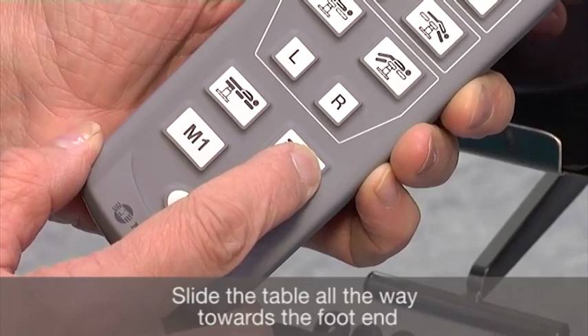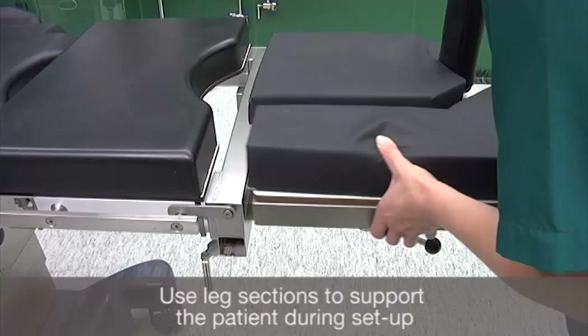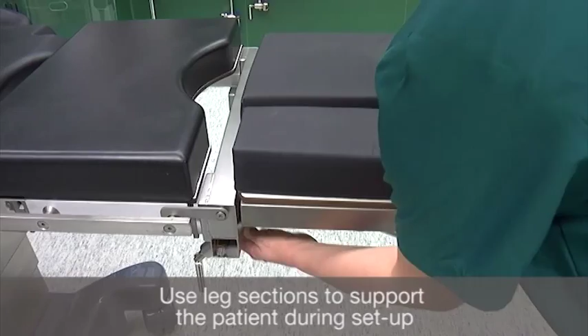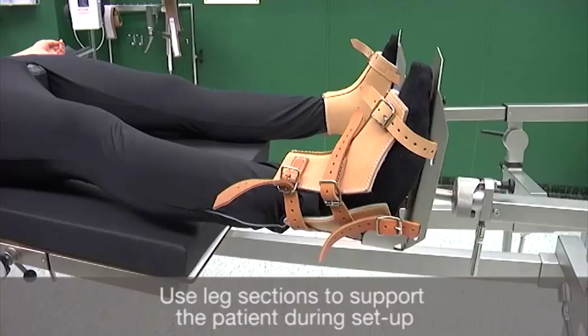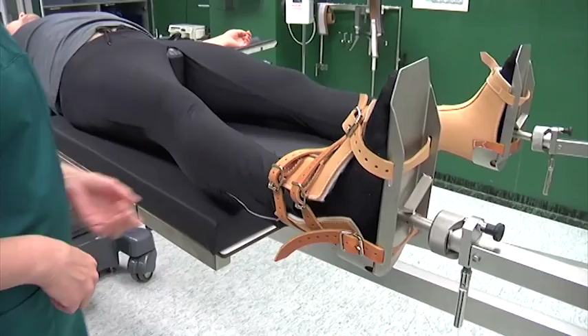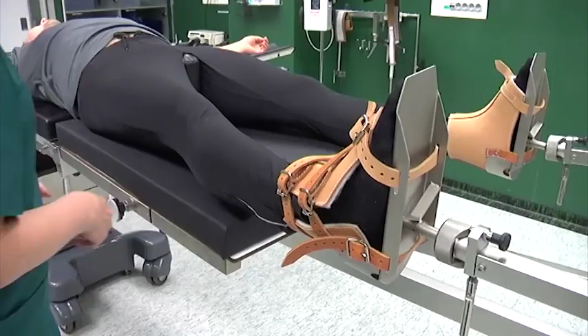Patient positioning should always be done by a trained healthcare professional. Always carefully follow the instructions in the manual of the device. If you have a sliding tabletop, slide the table all the way to maximize the access of the C-arm before setting up the traction device. Use leg sections to support the patient's legs during the setup. Attach the patient's feet to the traction device. Once the patient has been positioned, remove the leg sections.